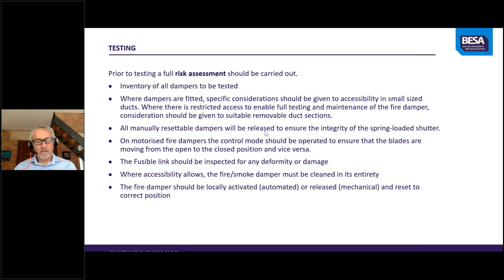So your report, again, you need to check with the previous report, as I said earlier, to make sure that modifications have been carried out. And if they haven't been carried out, of course, your new report needs to actually state this. And again, this is just a few items which are listed in the VH001, but your test report should include client information, the date, the name of the operative, register to include the damper location and ID number, and where the damper is not fully accessible due to inadequate access, you may need to make a note of that as well. Inspection results, including details of any failed operation, and an explanation perhaps of what the failed operation is and what recommended corrective action needs to be taken.